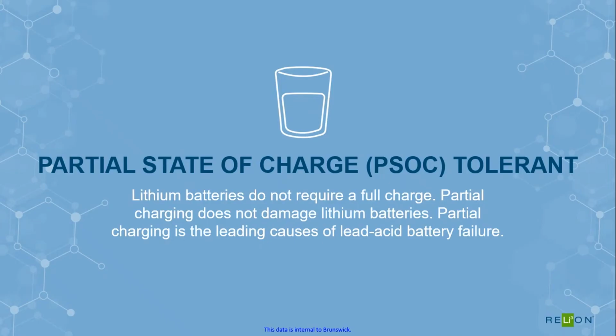Next, our lithium batteries don't suffer from partial state of charge. I like to think of them as partial state of charge indifferent. And partial charging is the leading cause of lead-acid battery failure. And it's not an immediate effect. It's a cumulative effect. Let's say that I didn't charge my batteries because I'm connected to solar panels and I didn't get enough sun that day. And that lead-acid bank was left in less than a full state of charge. It's cumulative, and it all adds up. Every time they're left that way for an extended period, the battery deteriorates a little bit more and ultimately leads to the early failure of that lead acid battery.